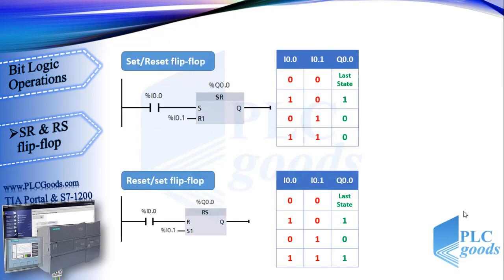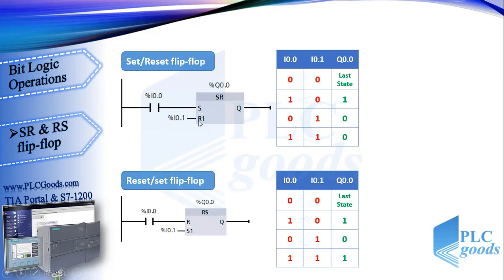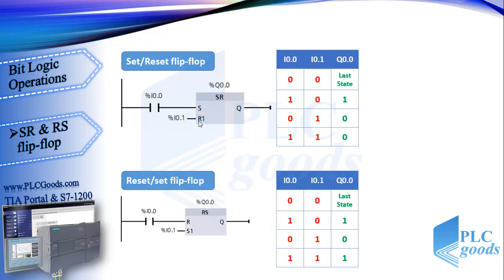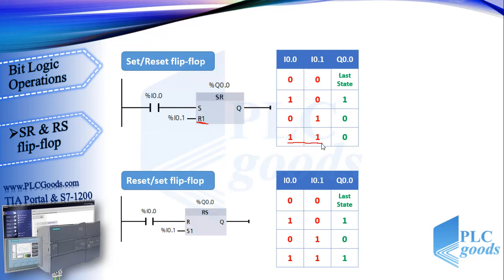These have both set and reset instructions which have been explained before. Here take care of SR and RS. As you see, at set reset flip-flop, the reset input is lower than set. So if both inputs, I0.0 and I0.1 at this program, are activated, CPU first decides to set output to 1, then decides to reset it to 0. So its final decision is resetting output to 0.